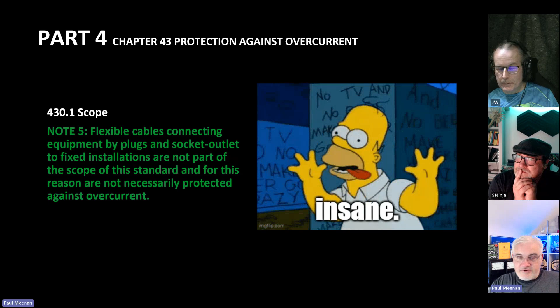43331. These numbers, I still prefer when it was dash. Where automatic disconnection of supply is inappropriate, the device protecting a conductor against overload may be installed along the run of that conductor if the part of the run between the point where a change occurs, i.e. cross-sectional area, so if you've gone from a 2.5, let's say realistically you go from a 35mm armour down to a 2.5, let's say. Some people have done that.